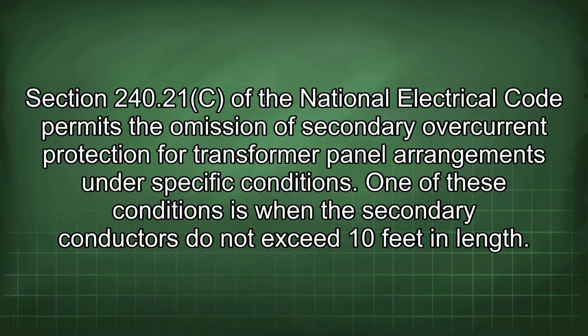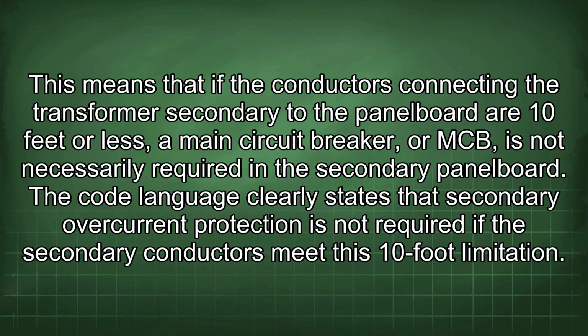240.21(c) of the National Electrical Code permits the omission of secondary overcurrent protection for transformer panel arrangements under specific conditions. One of these conditions is when the secondary conductors do not exceed 10 feet in length. This means that if the conductors connecting the transformer secondary to the panel board are 10 feet or less, a main circuit breaker, or MCB, is not necessarily required in the secondary panel board. The code language clearly states that secondary overcurrent protection is not required if the secondary conductors meet this 10-foot limitation.